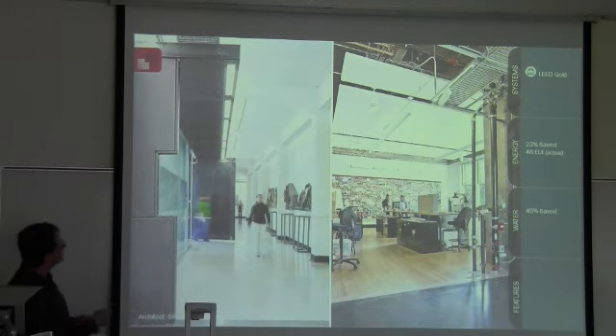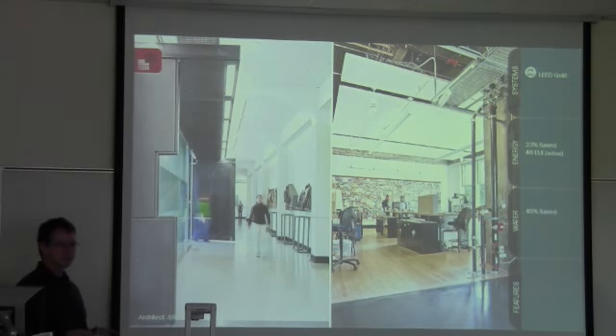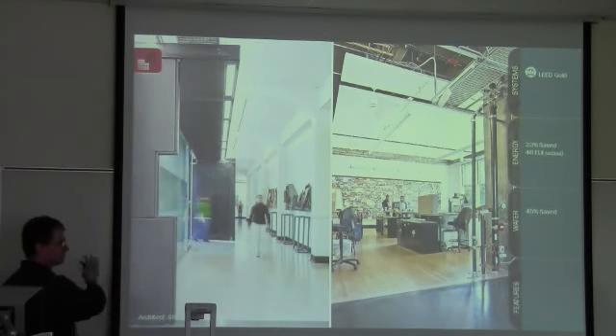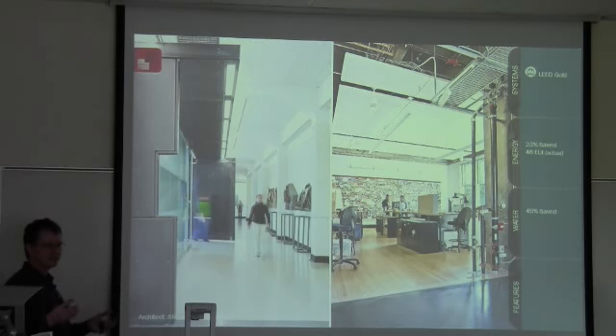One of the things that was done is this building used to have a multi-zone type of HVAC system, which is very inefficient. A lot of simultaneous heating and cooling with multi-zones. But we were able to take that infrastructure and turn it into a dedicated outside air system. So very economical to take ducts that go to every classroom and convert them from mixed air to outside air. And they were much larger than they needed to be, so the pressure drop was very low. Ended up being a great thing for the building.